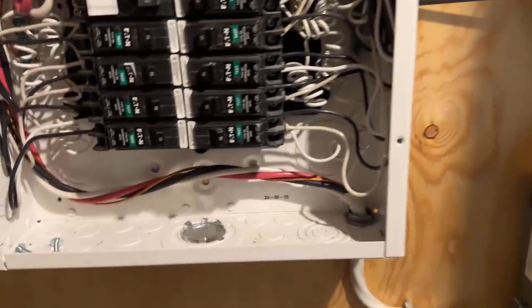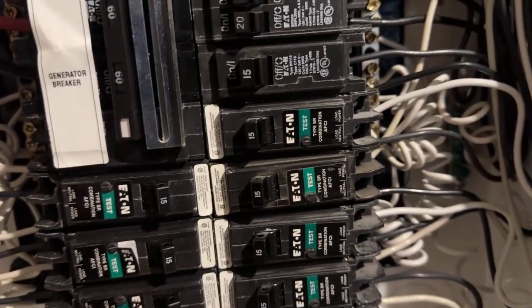As electricians, when we think of arc fault breakers we tend to cringe, because many of us have dealt with nuisance tripping. There's a certain brand out there that's notorious for it — I'm not going to name names, but they start with 'S' and end with 'mens.' Anyway, when we got the call today about an arc fault tripping regularly, we immediately thought it was a bad breaker. But actually that wasn't the case — this home has an Eaton panel, and from our experience the Eaton arc fault breakers work just fine.